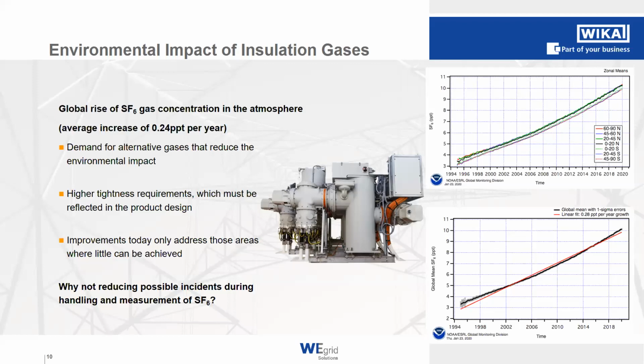So these tightness requirements can either be that the gas density in our gas compartment cannot leak, but also that we don't get the humidity from outside in our gas. Also, we are currently making improvements. That is definitely the case. We already have alternative gases for insulating the gas compartments. But these gases are usually, at the moment, used in the middle voltage range, and therefore the gas compartments are just smaller. So still in the high voltage range, with the big gas compartments, SF6 is the only gas which is used.